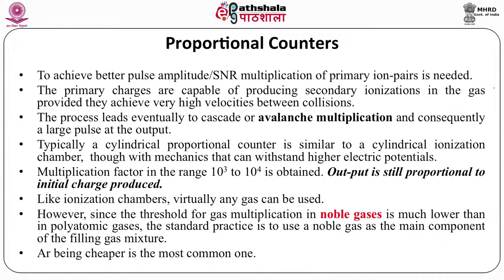After the ion chamber region, there is a proportional region where the pulse height or charge collected is proportional to the initial ionization produced. This is achieved by increasing the voltage applied across the gas detector to improve the signal-to-noise ratio. The primary ions produced by ionizing radiation start producing secondary ionization, leading eventually to cascade or avalanche multiplication and consequently a large current or charge pulse at the output. The signal amplification in a proportional counter is 10³ to 10⁴ compared to an ion chamber.